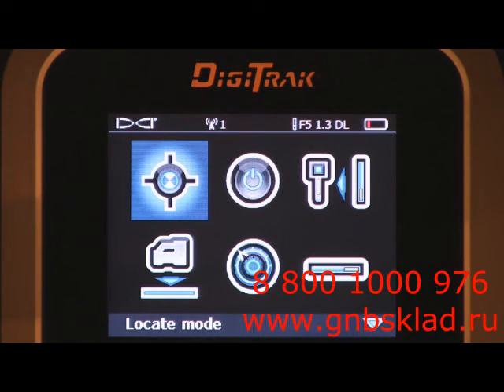Before we do so, let's verify a few things. I'm going to go to the locate mode screen. I'm going to click it. Okay, so now I'm verifying that the transmitter is in fact sending out signal. The receiver is set to pick up that specific frequency. I'm getting 566 counts of signal. I'm good to go.